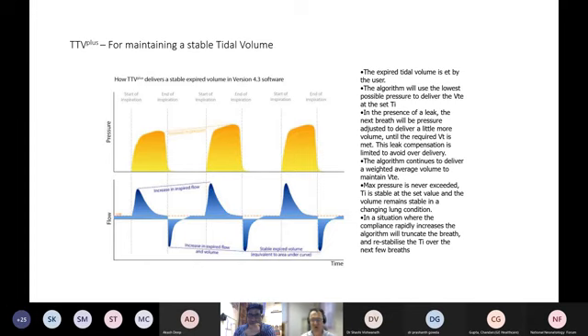The rough rule of thumb is 3 to 4 mils per kilogram. That is a rough rule of thumb, although that's quite universally used. But that allows us to give a good estimate, and we can put a controlled estimate into the ventilator of a safe volume that we can deliver to baby's lungs. And this has given rise to lung protective ventilation methodologies, and volume guarantee, or TTV, is really at the center of that. And that required the use of the flow sensor technology to achieve that.